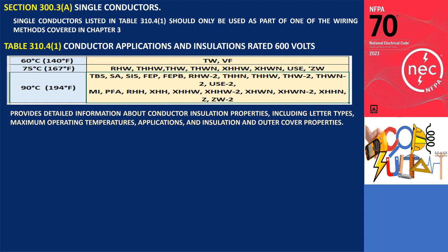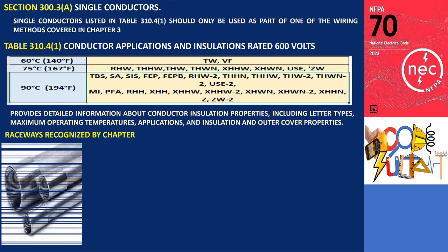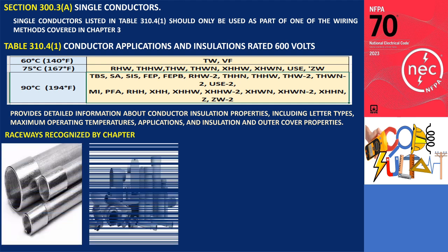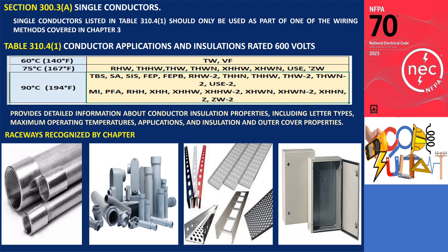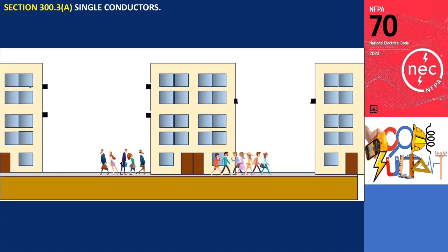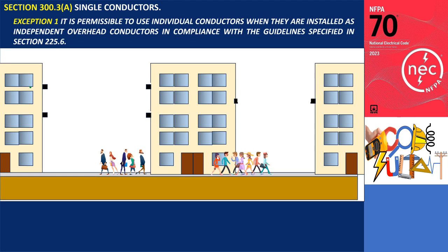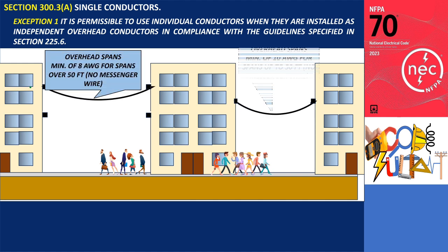These conductors listed in the table should not be used independently as overhead conductors unless they are part of a cable assembly or adequately protected and supported by conduit, tubing, raceway, cable tray, or enclosure. However, if the individual conductors are installed as separate overhead conductors in compliance with Section 225.6, they are not subject to the requirements of Section 300.3a.